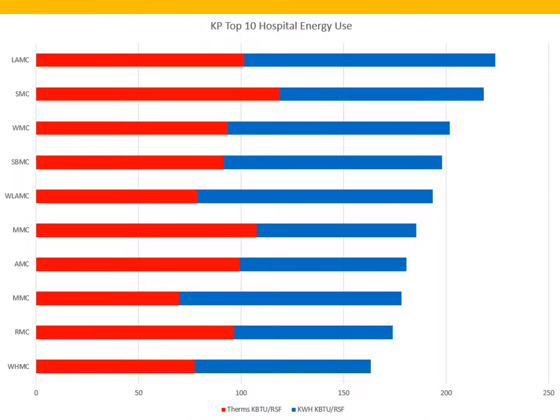I say that so I can brag on the next slide, showing Kaiser's top 10 hospitals. Our lowest is around 150 to 160, but we quickly climb up to 200 kBTU per square foot per year. I make it my business to know where the rest of the leaders are in North America, and to my knowledge nobody has beaten 150 in the U.S. or Canada. Some hospitals designed to 100 with energy models for 100 but ended up coming in at 160 or 170.